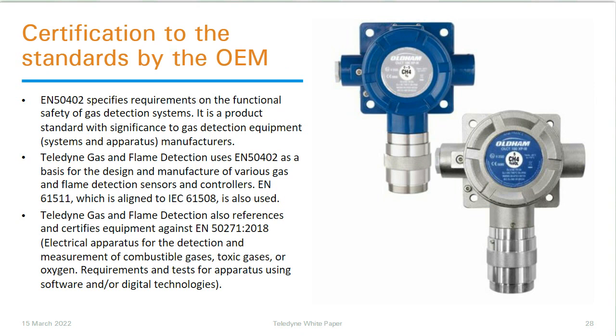The EN 50402 is one of the norms or standards that specify the requirements on the functional safety of gas detection systems. And ultimately it's a product standard, so it's of specific relevance to Oldham within Teledyne gas and flame detection. That standard also refers to various other standards and also refers to how these products should be certified, what kind of testing should be done by Oldham or by Teledyne gas and flame detection to make sure that these products comply with the various different norms and standards.